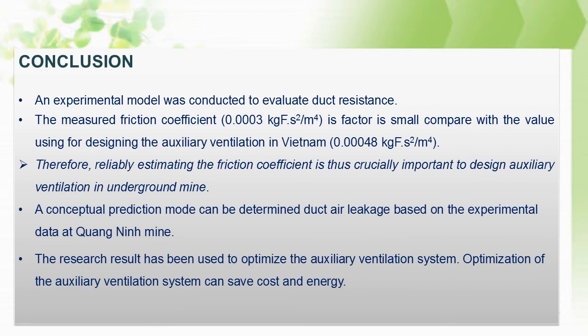Conclusion. An experimental model was constructed to evaluate the duct resistance. The measured friction coefficient is small compared with the value used in designing auxiliary ventilation in Vietnam. Therefore, reliably estimating the friction coefficient is important to the design of auxiliary ventilation in underground mines.